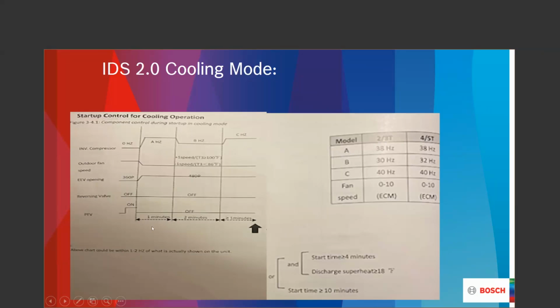And what we're looking at here is the progression of what we would call staging, if you don't mind, to a Y1 call. Because it's not like I have an old grandpa-type air compressor where when the compressor came on through the contactor, we were on. At that point in time, with that old style, we drew a whole lot of inrush locked rotor amps, and the lights blinked, and everybody knew that the compressor was on because it was painful outside on the concrete pad. This particular system, when this unit starts up, we're at a very, very low amp draw, basically less than 1.7 amps. So no light blinking, things like that.